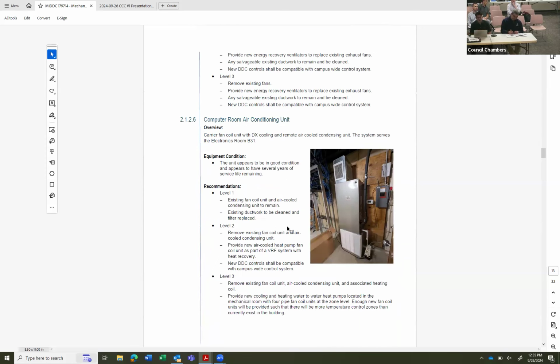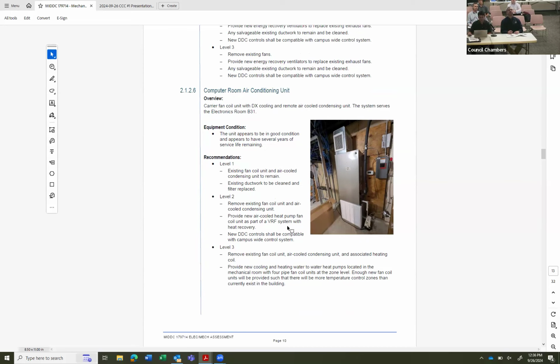And the computer room air conditioning unit serving the electronics room in the basement. This equipment appears to be in good condition, and it's probably several years old, so it has several years left of the expected service life. So I would recommend for the level 1 upgrade, where we're not changing the system wholesale, we can keep this unit and simply replace the filter and clean the ductwork as normal maintenance.